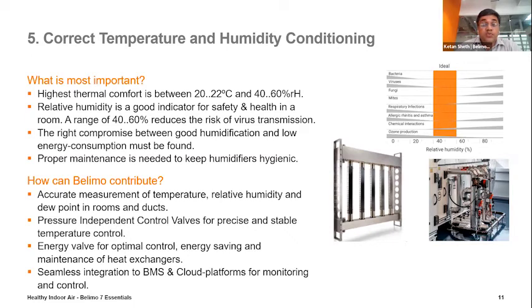Since these are performance devices, the data recorded by these devices in different ambient conditions, the conditions within the building, and what control action it has taken can be seamlessly integrated to the BMS. Our energy valve is basically an IoT device, and we provide Belimo cloud services. So all this data can go directly to the Belimo cloud. Analytics can be performed on that, and performance dashboards can be provided to the customer for better performance of the system, and it also provides the control.